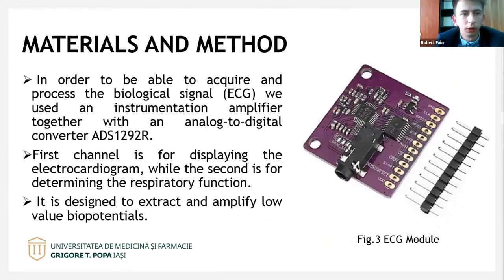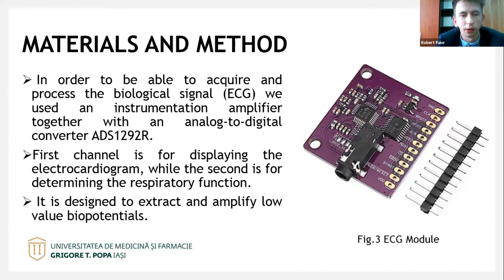In order to acquire and process the biological signal — ECG — we use an instrumentation amplifier together with an analog-to-digital converter. The first channel is for displaying the electrocardiogram, and the second is for determining the respiratory function. It is designed to extract and amplify low-value biosignals.